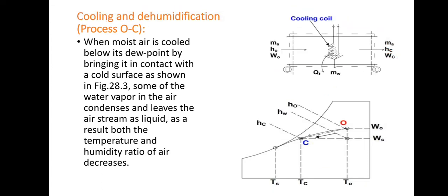So at the O point and W point, we have found the enthalpies, and from W to C we will consider the process as sensible cooling. So that means the cooling and dehumidification process is the combination of the dehumidification process and the sensible cooling process. Okay, now next one.